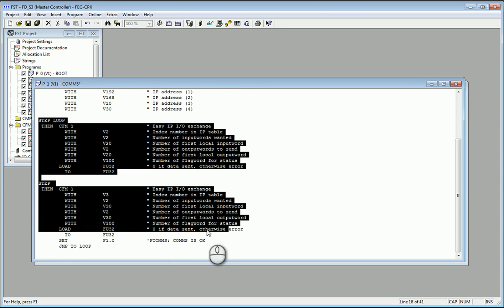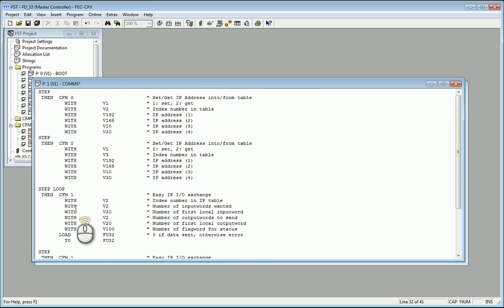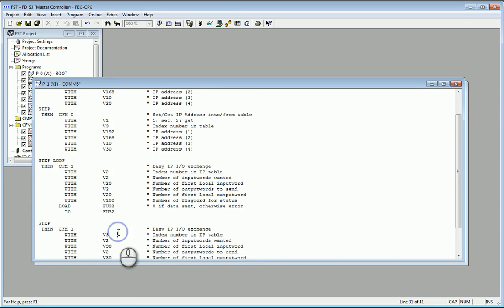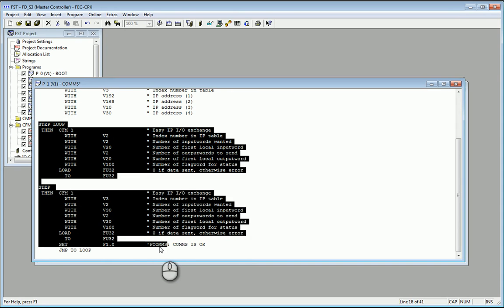So the inputs that you see on your master controller are constantly being updated, possibly thousands of times a second. P1 runs constantly, yep, that's right. Your P1 in this case will carry out all 4 steps for the first time, and then will constantly loop just the bottom 2 steps over and over again.